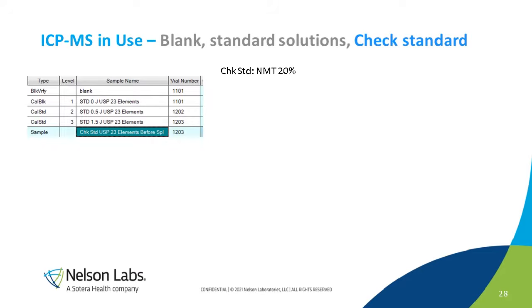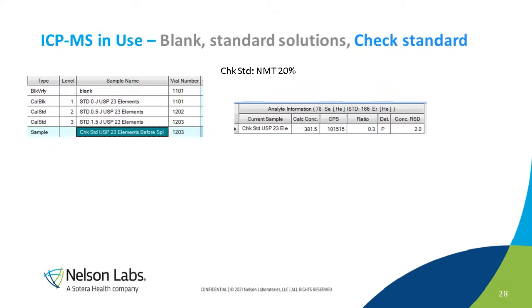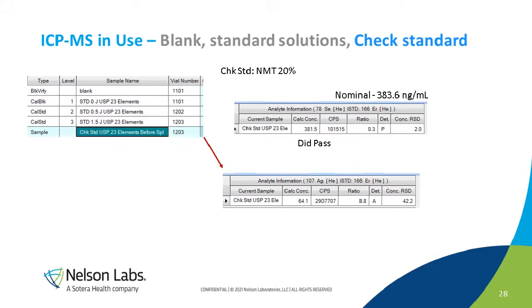Now we want to check our check standard. So actually the spec is going to be below 20%. So I'm just showing this specific one, selenium. The number is 381.5. And then the nominal number came from this, 383.6. It's good. Pass.